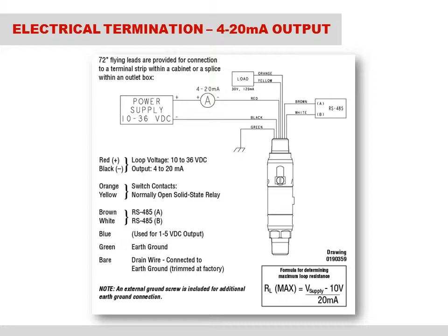Now let's take a look at the very important red and black wires. Those serve a multi-purpose role. The red and black wires supply power to the 815 PT instrument, or stated another way, the loop voltage is supplied via the red and black wires. The black and red wires are also required for a 4 to 20 milliamp output, and if needed, the HART communication protocol is also superimposed on the red and black wires.